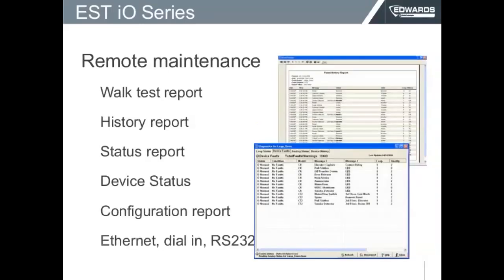On remote maintenance, instead of using two or three guys in the field, you can just send one. The guy makes sure you get connected, and once connected you can get reports from the walk test, history, status, service, devices, and configuration — everything. You can pull it via Ethernet, dial-in, or RS-232. You don't have to have one guy in front of the panel and another in the field. You just send the guy in the field to walk the site for testing, and when he's done you can connect remotely and pick up all these reports directly from the panel.